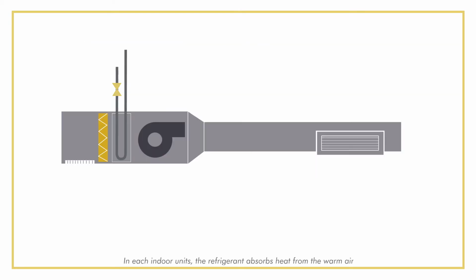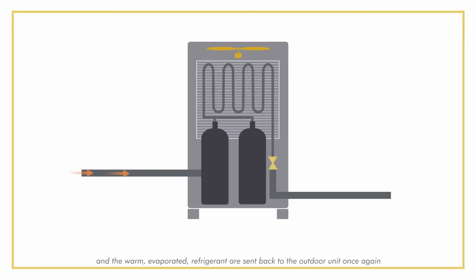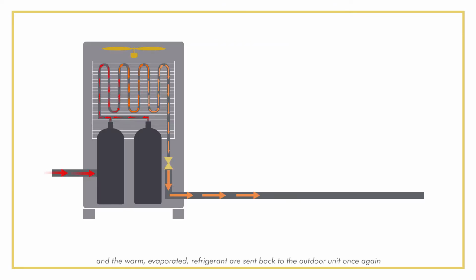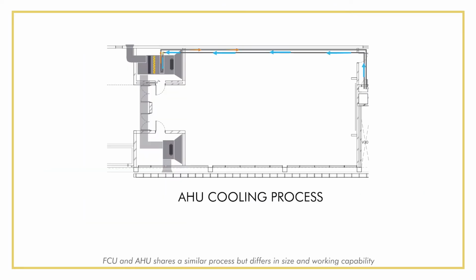In each indoor unit, the refrigerant absorbs heat from the warm air. Thus, the air is cooled down and discharged into the room, and the warm, evaporated refrigerant is sent back to the outdoor unit once again. FCU and AHU share a similar process but differ in size and working capability.